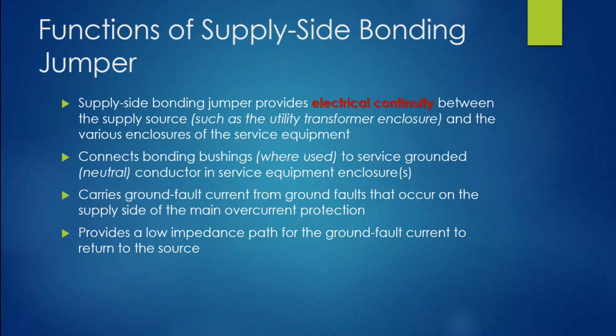Like you might have an open bottom switchgear, and you've got raceways coming in through a service lateral, and you still have to bond those raceways because they do have service conductors in them. So we're going to have supply side bonding jumpers over to those as well. So we'll cover that. It carries ground fault current from ground faults that occur on the supply side of the main overcurrent protection. Again, we talked about that.